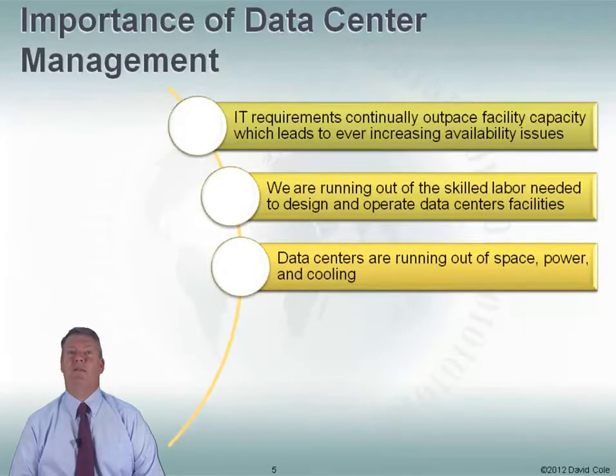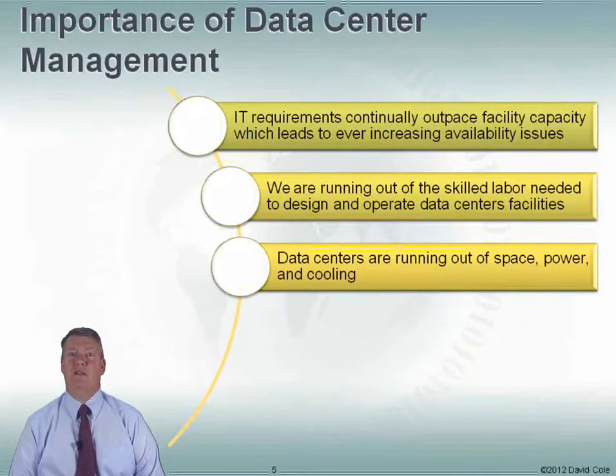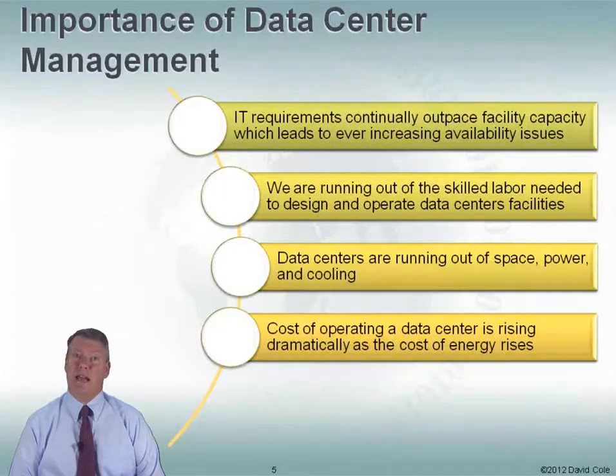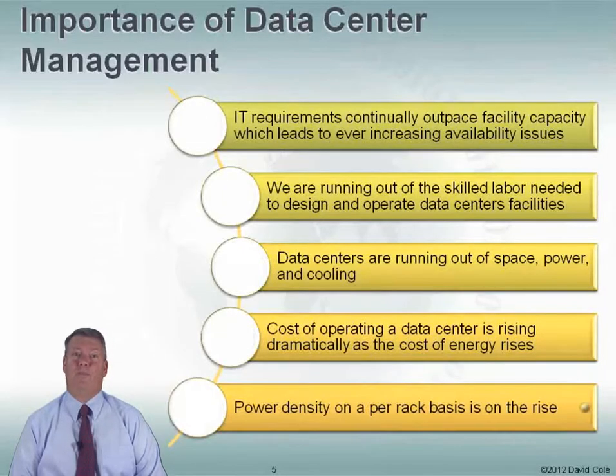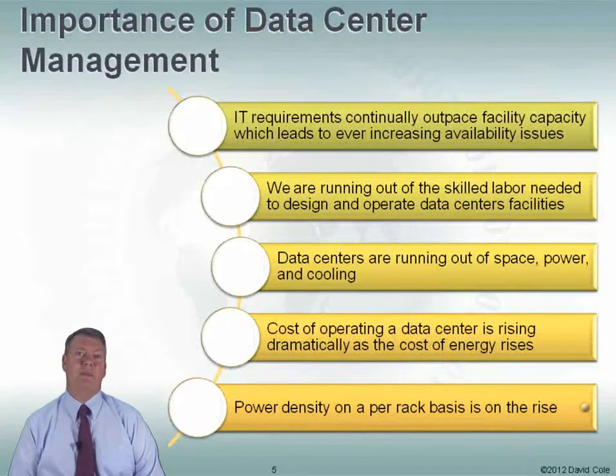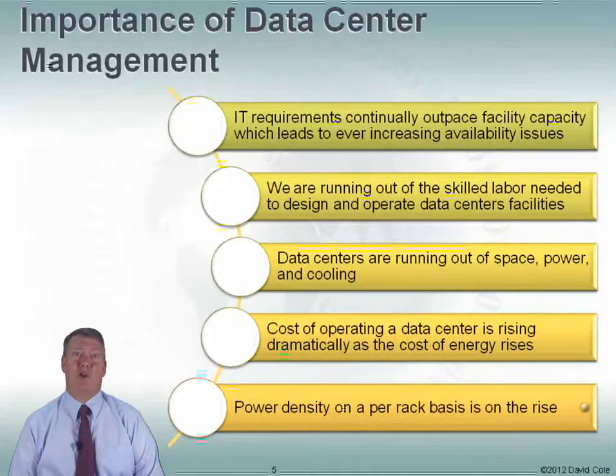Data centers are continually running out of the three big resources: space, power, and cooling. The continual issues we face in the data center are resource usage, particularly in space, power, and cooling. The cost of running a data center is continuing to rise — in fact, it's rising dramatically. As the cost of energy rises, the cost of operating a data center rises dramatically. And the power density on a per-rack basis is also on the rise. What used to be one, two, and three kilowatts per rack is now five, six, 10, 15 kilowatts per rack, creating issues with both powering and cooling.